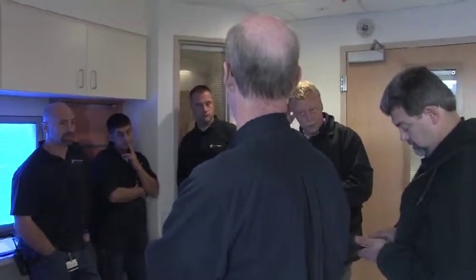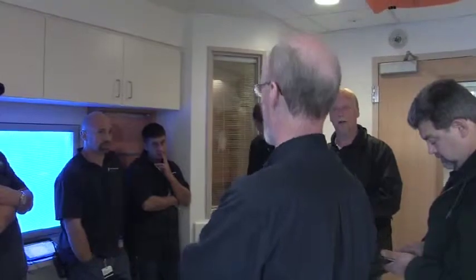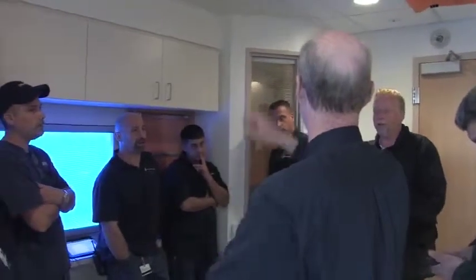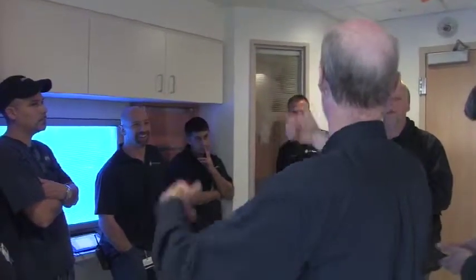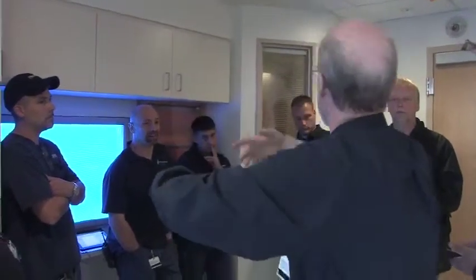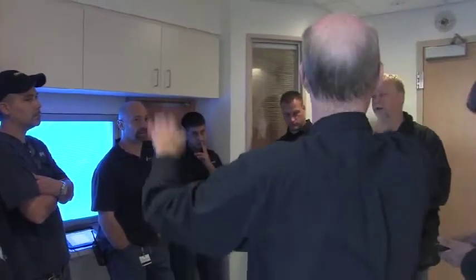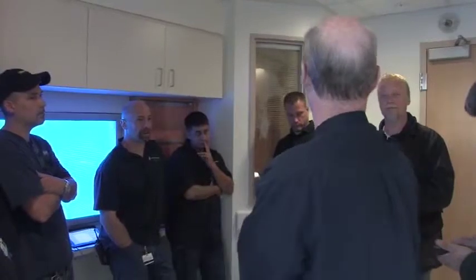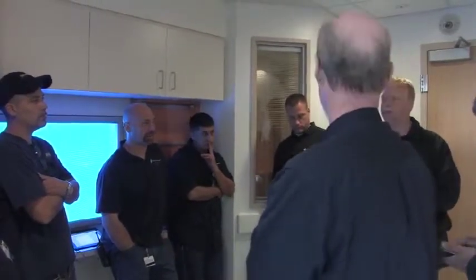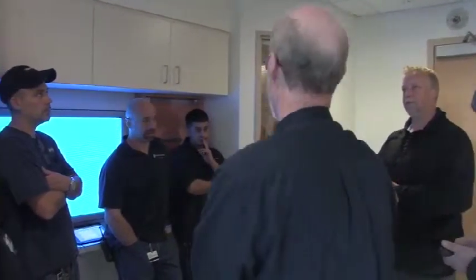Well, we don't have that in the main building. Oh, you don't have it? No, we found out the hard way. If you shut the fans off and the air handler's still running, it back feeds. It blows everything you collected on your filter. Blows everything. That was a big snowstorm. And in the immune suppressed patient's room, it's not a good thing. So here, we won't have that.